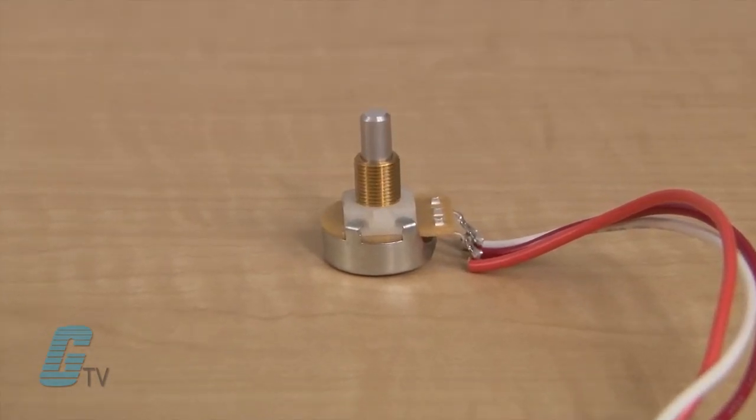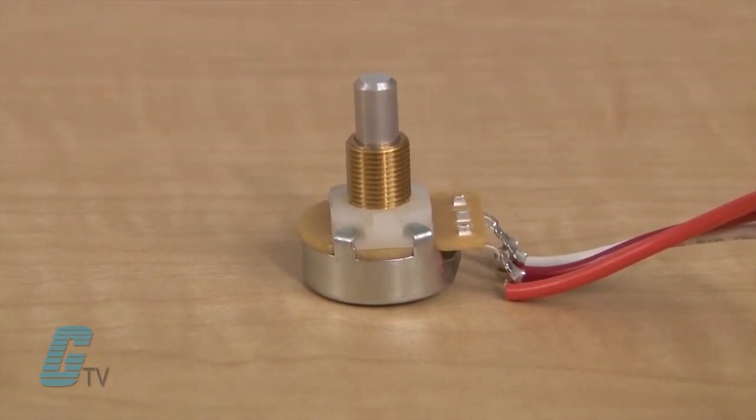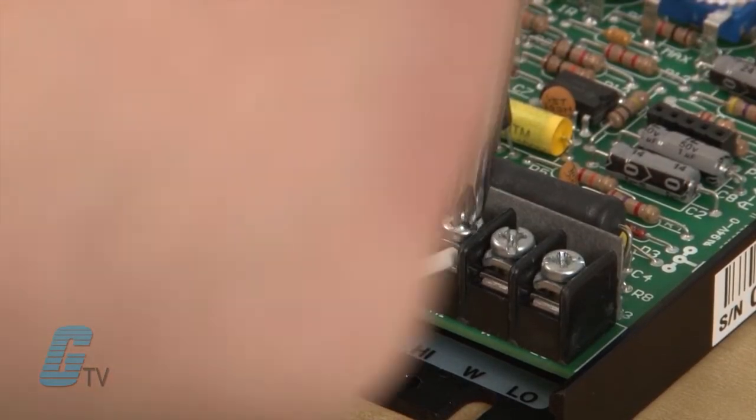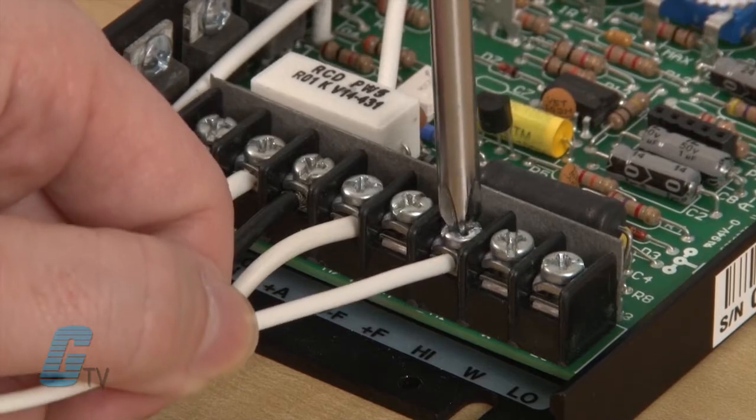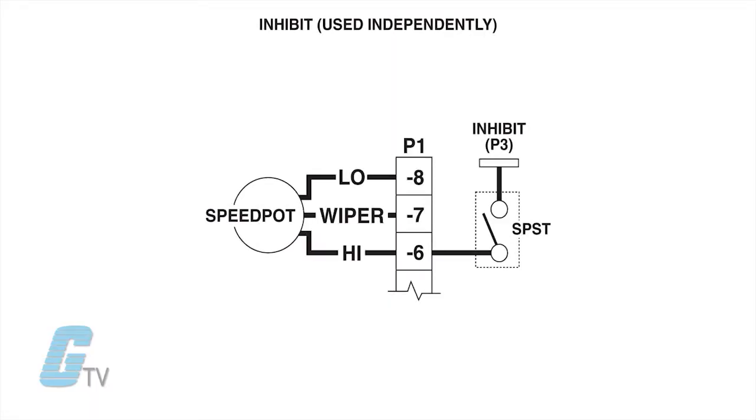My last three connections on the terminal are for the potentiometer. The sixth terminal is for the high connection on the speed pot with the white wire. It is also a 12 volt connection where an inhibit switch can be installed between this terminal and P3. This requires a single pole, single throw switch.